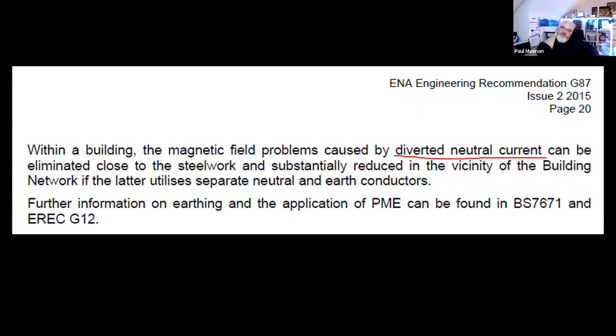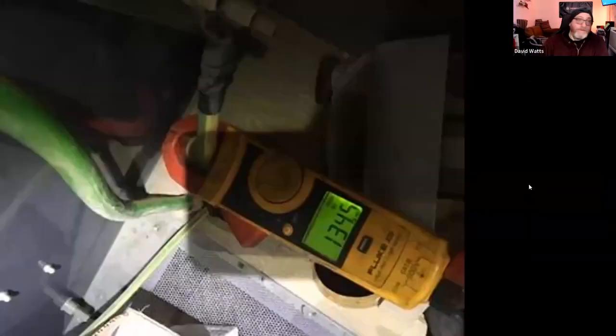Yes, you mean that section that most electricians' tutors go, move on. Move on. Yeah. Circulating currents. This phenomenon will create circulating currents in the building structure. It will, indeed. I'm more interested in the magnetic field issues, whether there's a compatibility issue there or an overwhelming of transmitter equipment, because I know that's what Paul's thinking. Well, it's AC, so it's going to be an alternating field. So you're going to get a great big 50 hertz antenna in there. Or if you've got triple-n circulating, you've got a 150 hertz antenna. And higher with some of the harmonics. And higher, the more there are.